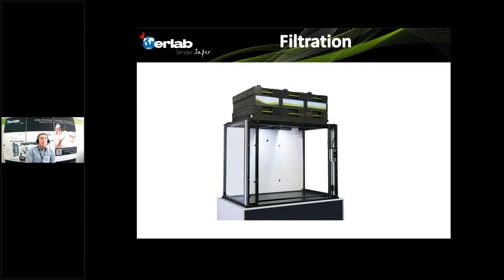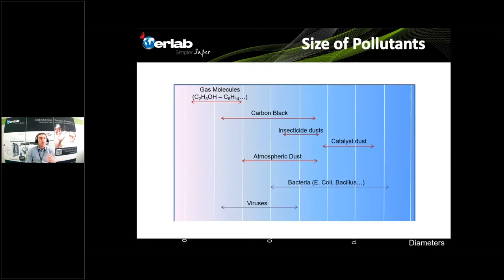The second important technology used for recirculatory filtration fume cupboards — called fume hood or fume cupboard depending on where you are in the world — is the ability to filter. Before talking about the technologies themselves, when we talk about air pollution, we have to consider that it can be a mix of different kinds of pollutants: gas molecules, liquids or solids, with a size range from 0.1 nanometers up to 1 millimeter.